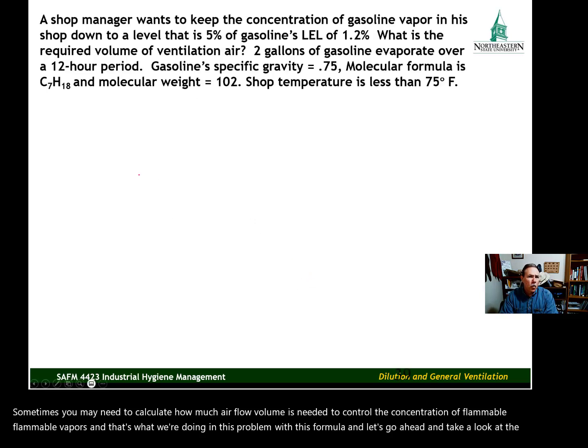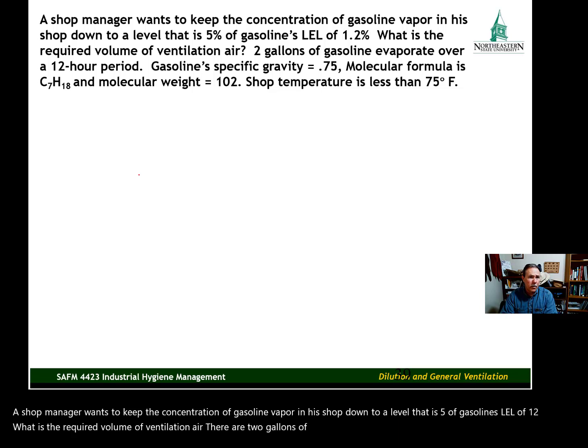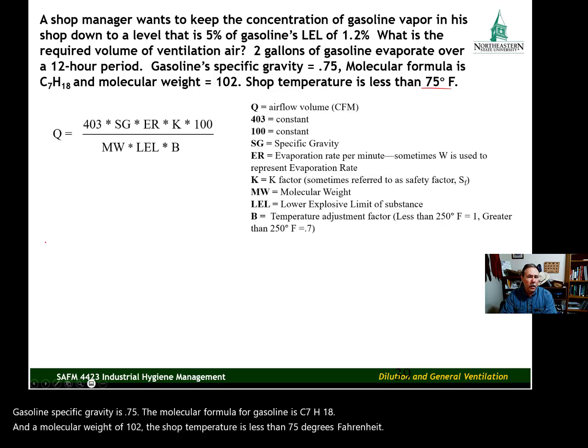A shop manager wants to keep the concentration of gasoline vapor in his shop down to a level that is 5% of gasoline's LEL of 1.2%. What is the required volume of ventilation air? Two gallons of gasoline evaporate over a 12-hour period. Gasoline's specific gravity is 0.75, the molecular formula is C7H18, and molecular weight is 102. The shop temperature is less than 75°F.